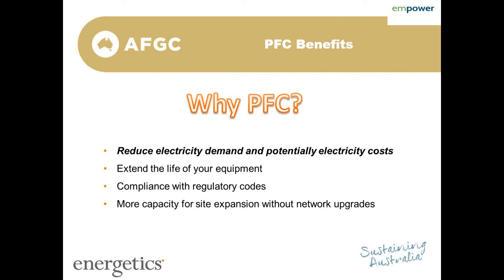Often they're not too rigorously enforced, but there are many requirements for Power Factor on site. Depending on the size of your supply voltage, the kilowatts that come to your site, and the size of your demand on site, there are different requirements — from a minimum of around 0.75 Power Factor up to very large loads on large transformers requiring about 0.98. Typically, 0.8 is the minimum. If you're getting really low, you may have requirements to improve that.